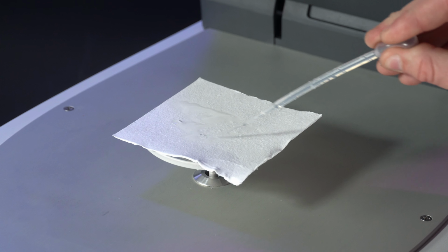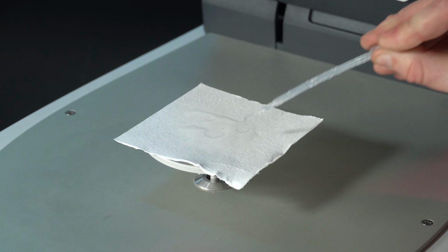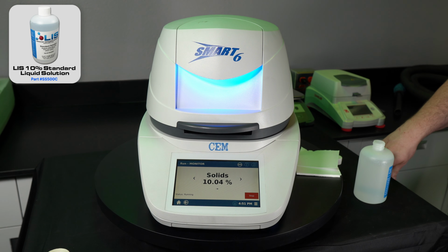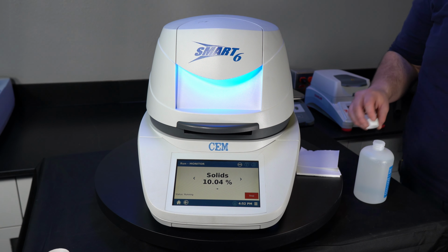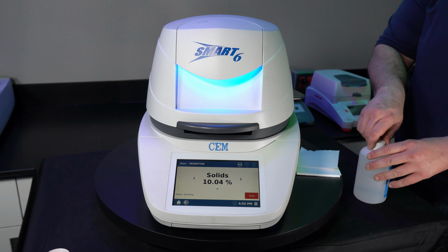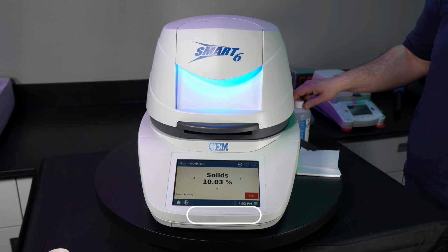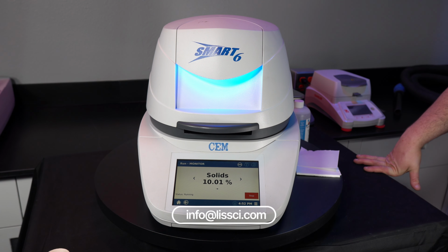Close the lid and run a few tests with our LIS standard solution. If there's no inconsistencies with these tests, run a normal sample test of your product. If there's no inconsistencies with the instrument, the issue is now resolved. If there's still issues, please contact us by email at info@lissci.com or go to our website and fill out a service request form.